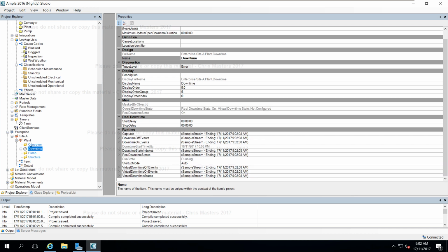What I'm also going to do is change the display order index again to promote this reporting point so it always sits at the top, because obviously as the configuration gets larger I need to be able to see what I'm doing. And then I'm also putting these folders in this hierarchy in here. I want these to be in a sequence or an order that an operator would understand. So within this plant, typically you're laying items into this structure that makes sense in terms of the process flow more than anything.